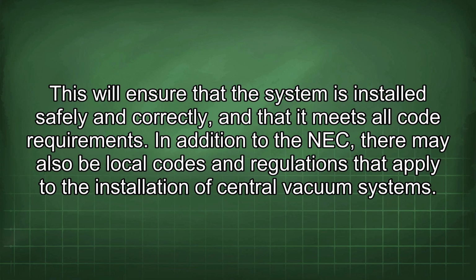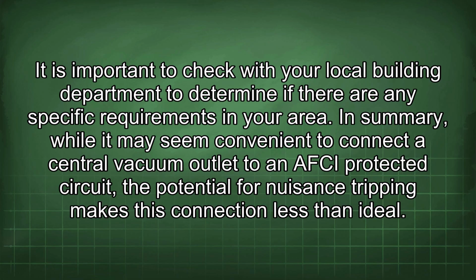In addition to the NEC, there may also be local codes and regulations that apply to the installation of central vacuum systems. It is important to check with your local building department to determine if there are any specific requirements in your area. In summary, while it may seem convenient to connect a central vacuum outlet to an AFCI-protected circuit, the potential for nuisance tripping makes this connection less than ideal.